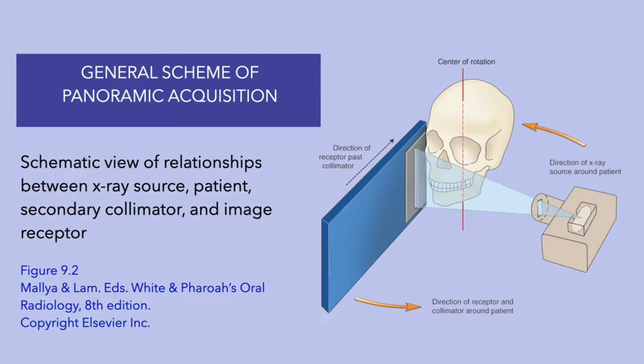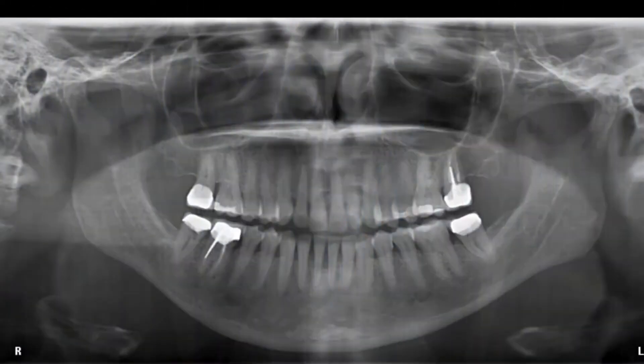This graphic demonstrates the general scheme of making a panoramic radiograph. An X-ray source and receptor rotate around the patient's head. The X-rays are collimated into a narrow vertical beam at the source and again at the receptor. The receptor moves past the collimator during the exposure cycle, acquiring sequential vertical images of the patient's jaws. When viewing a panoramic radiograph, you will recognize that superimpositions from the contralateral side of the jaw are not readily apparent.